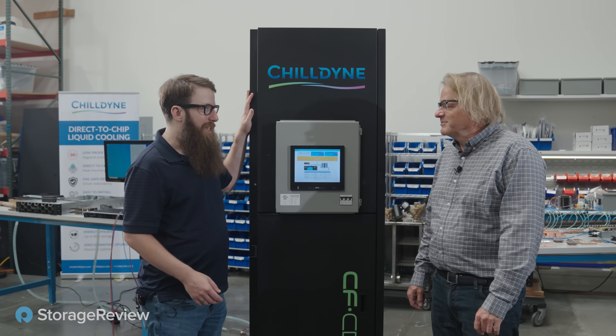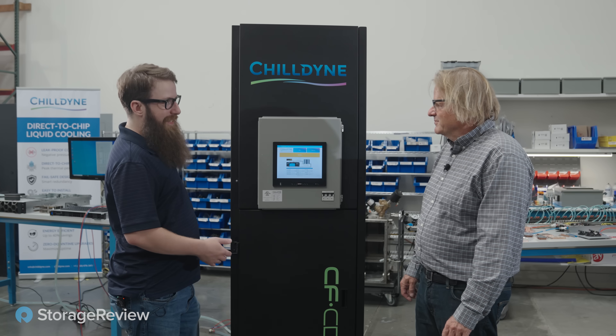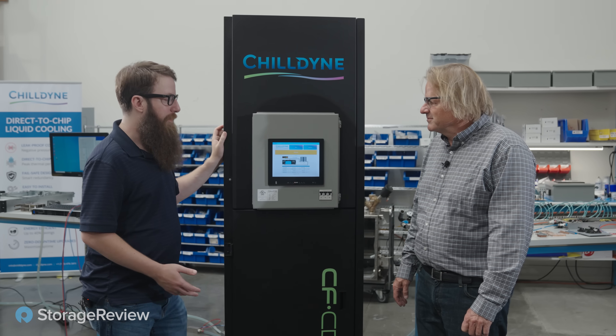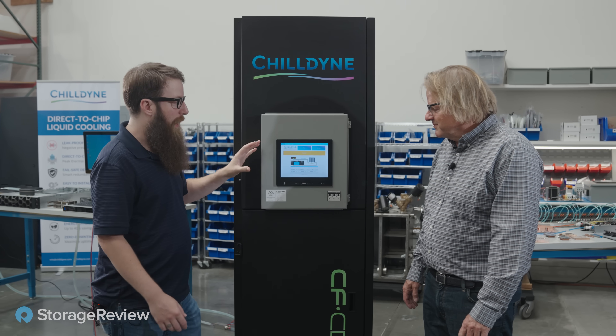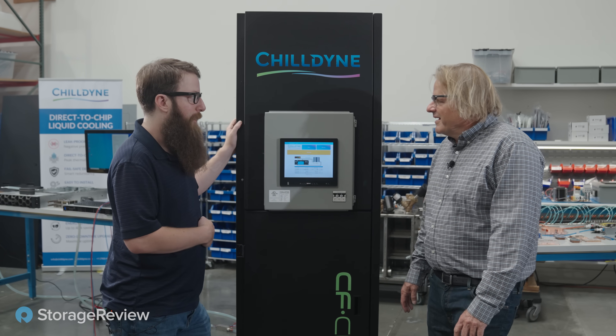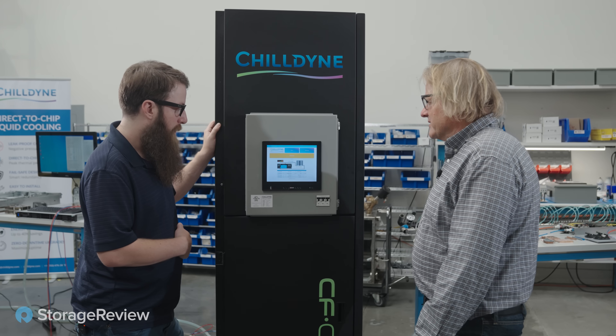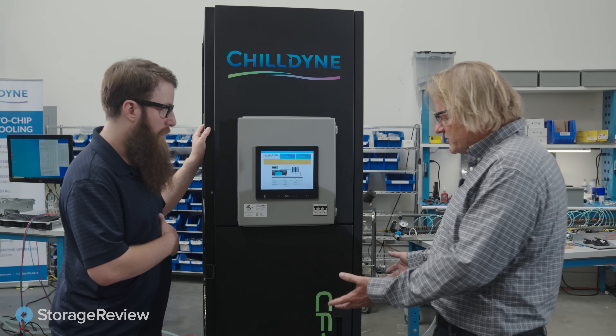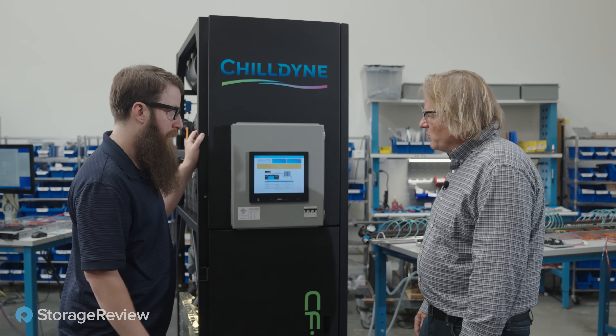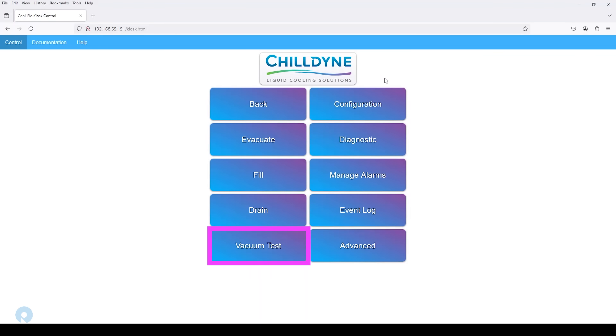All right, Steve, so we just got our new Chilldyne CDU in our imaginary data center here that we've mocked up. What's the first thing that I have to do? We got our power switch on, so we're live on our screen. So what you're going to have to do — it's pretty simple — is if you just installed this in a data center and filled up the CDU with water, go ahead and hit vacuum test.